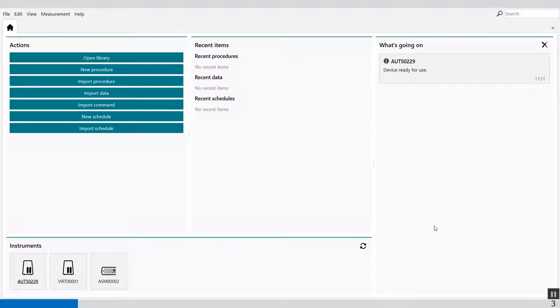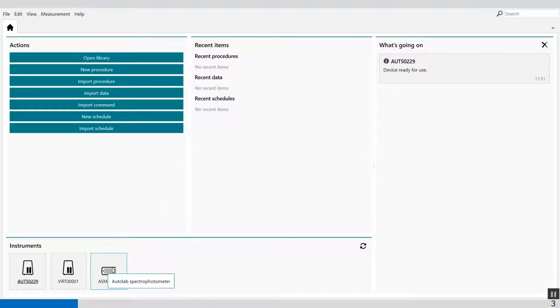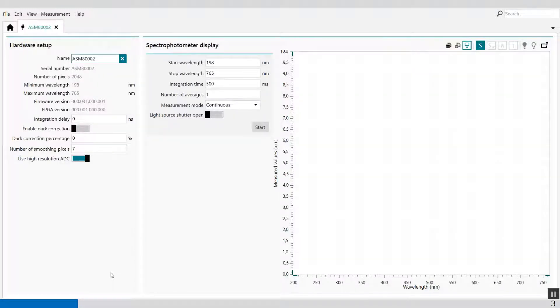Welcome to the NOVA software. In this video I'm going to explain the manual control of the spectrophotometer. In the overview of the NOVA software you will see this icon — Autolab spectrophotometer. Double click on it and the manual control becomes available for the spectrophotometer.